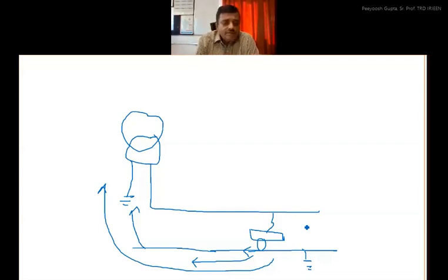But why have we adopted such a system? For safety, we want that in case our overhead equipment falls to the ground, we need high current to flow so that our relay acts. All our structures like poles, masts, even foot-over bridges, we make earthed, so that if live touches the mast, because of the bonding available, return current flows and our relays act and disconnect it.